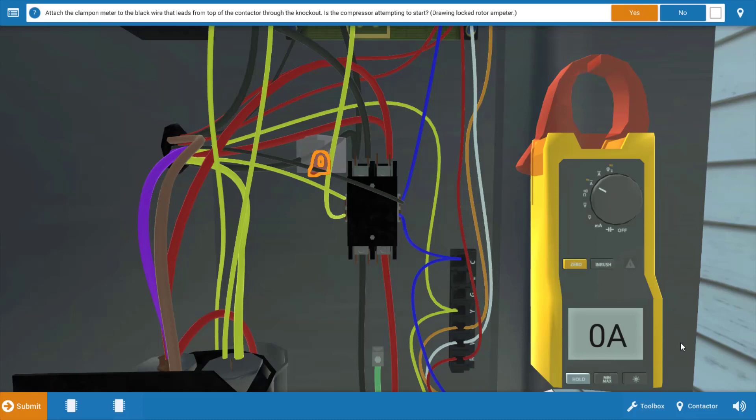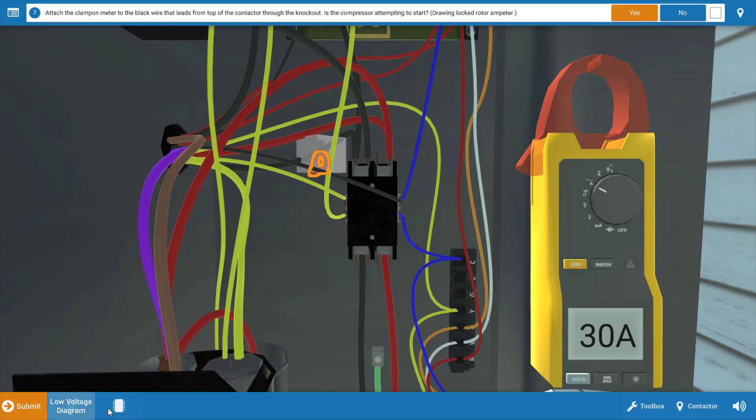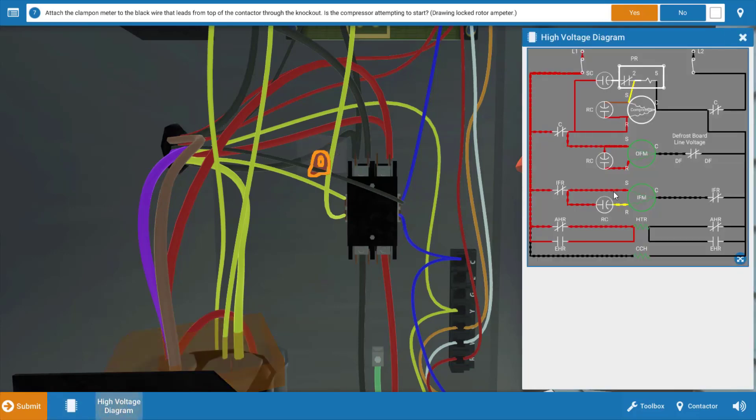This is referred to as locked rotor amperage, meaning that compressor is trying to start, is drawing locked rotor amperage, and then with that high amperage is cycling off on its internal overload. Now, this most likely indicates a starting circuit problem. And let me show you what I mean by this. We're going to click on the wiring diagram here for a second.